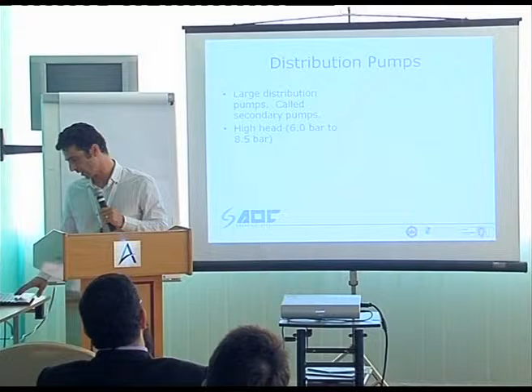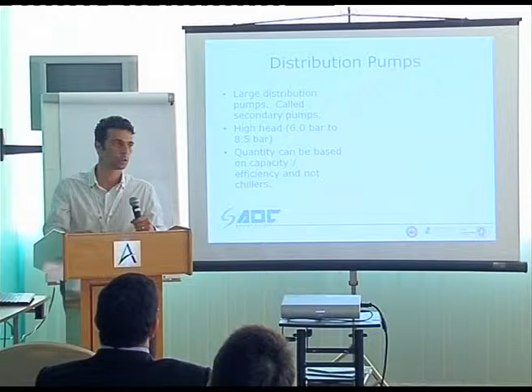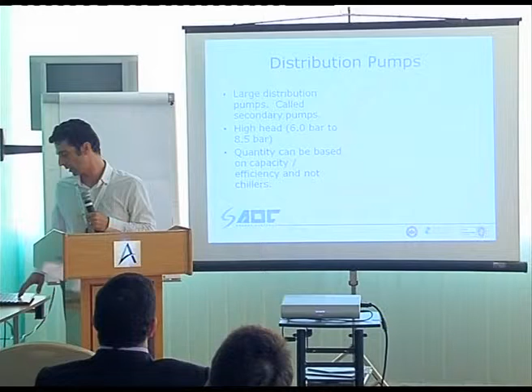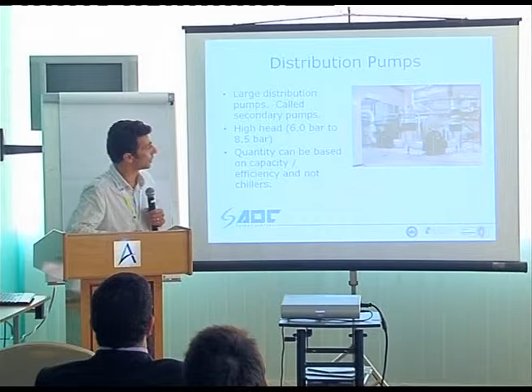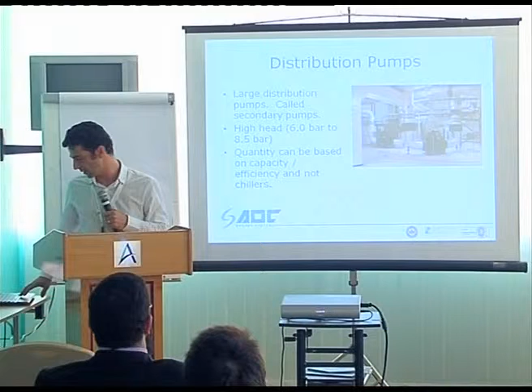The quantity depends on the capacity and doesn't depend on the number of chillers that you have there. Remember, in designing or constructing anything, the larger the machines, the fewer of them, means less headache for you, whether during construction or during operation of the plant. So generally, choosing a lower number of machines is better for you. And this is how a pump would look because it's working on the chilled water system. It has to be insulated.